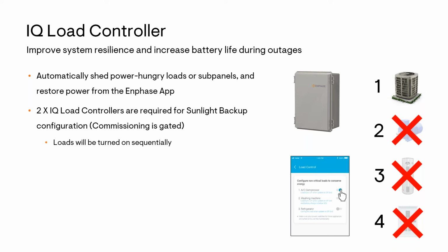There's also a new load control setting specifically for sunlight backup, which is designed to essentially power the loads on one at a time, starting at 9 o'clock in the morning, which is going to reduce the chance of a microgrid collapse. And there's also a gap between those loads turning on, so that if there is a load that continually overloads and shuts down the microgrid, then that load will be excluded from the startup sequence with the next try.